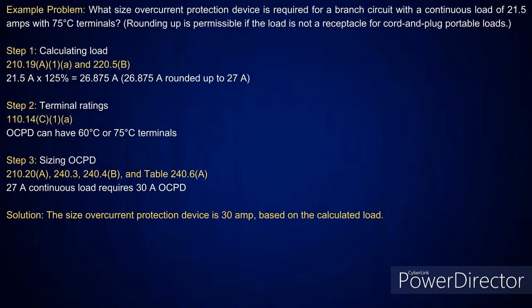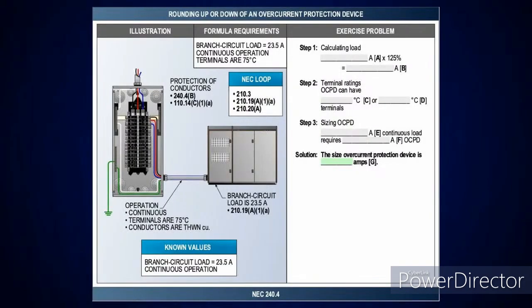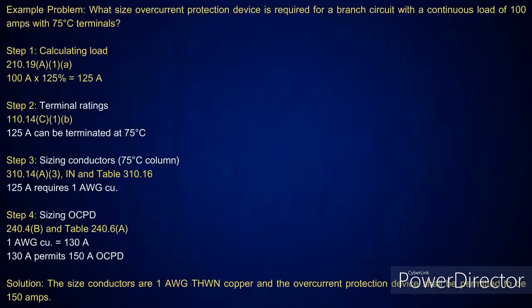But they're going to ask you here, what size overcurrent protection device is required for a branch circuit with a continuous load of 21.5 amps with 75 degrees C terminals? Well, all I'm going to do here, if it's continuous, I take it at 125%. So 21.5 amps times 125% is 26.8. We're just going to round it up to 27 amps. What is the next size above that for table 240.6(A)? That's a 30 amp overcurrent protection device. And then you get your illustration here. Same calculation. I've got 23.5 amps. It's continuous. I take it at 125% and then size my overcurrent protection device for that.